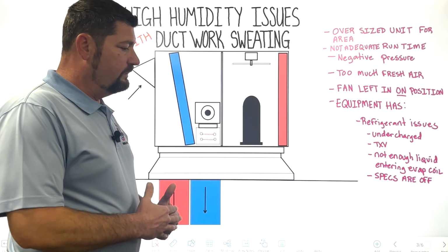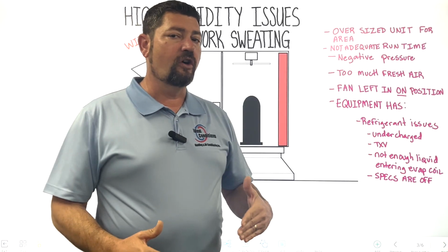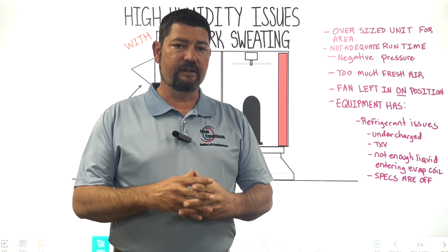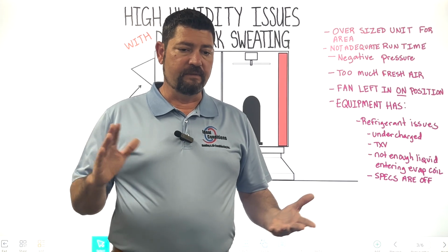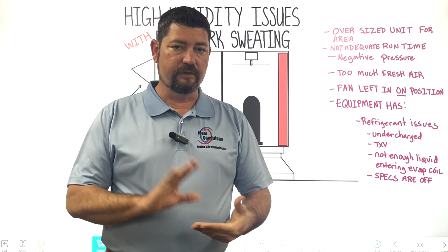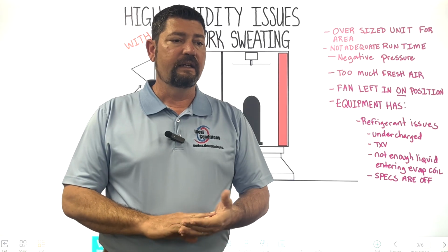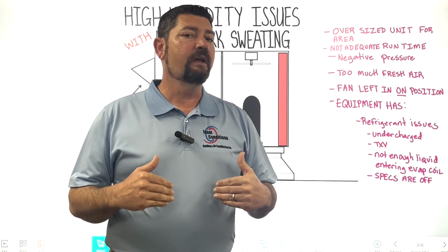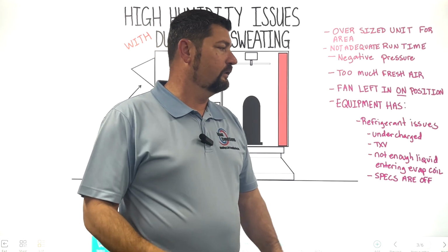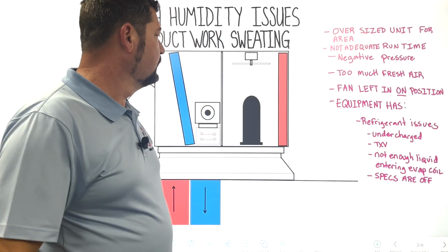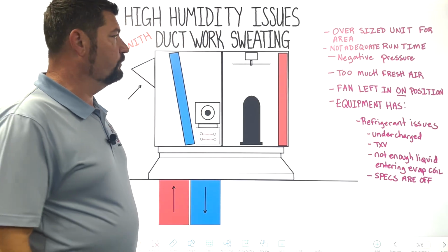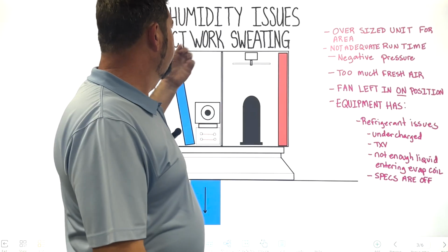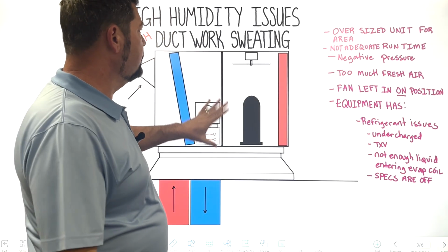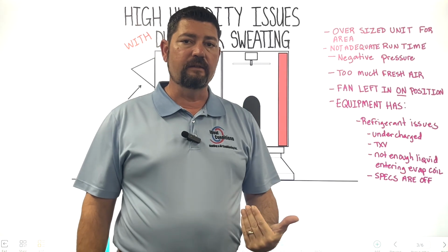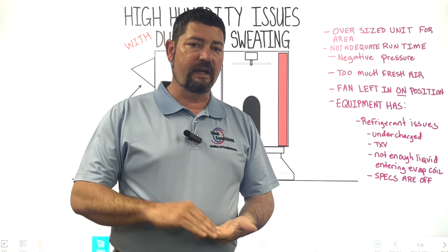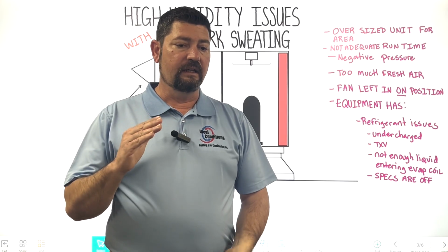But if you find that the unit is not running long enough, right, the thermostat's just satisfying, it's meeting its temperature demand, whatever the set point is, too quickly, then we're not going to remove enough humidity out of that space. We call that a short cycle. And so we see that a lot in commercial. So that is one thing that would cause high humidity. Now, that's not going to cause your ducts to sweat, right? That's just going to have a very high humidity.